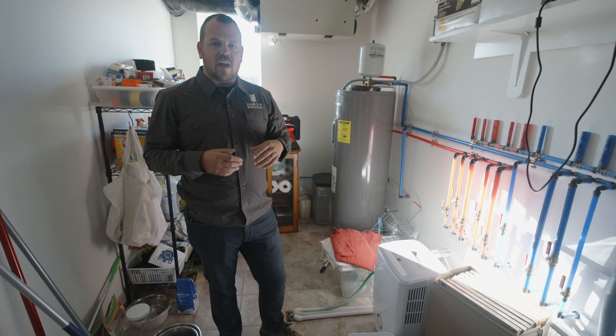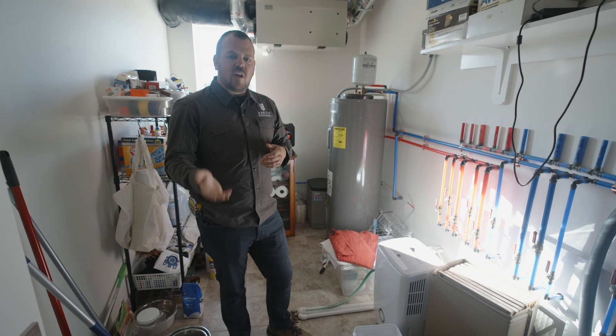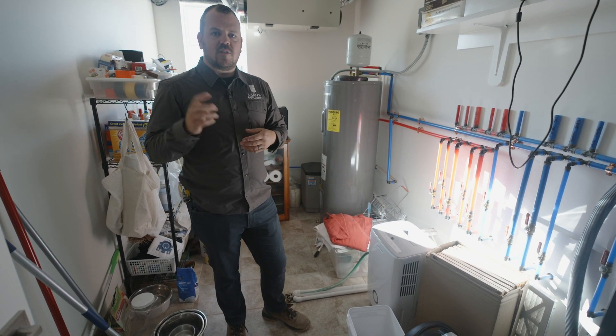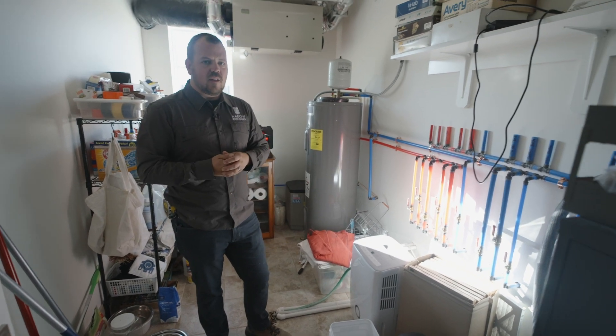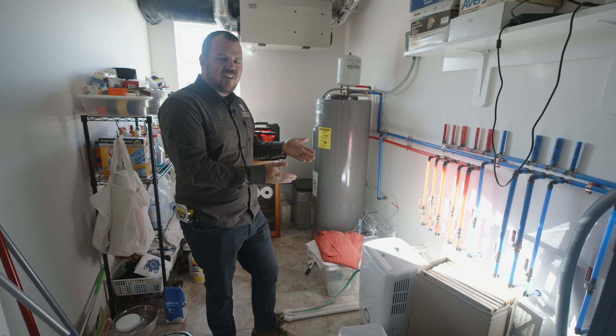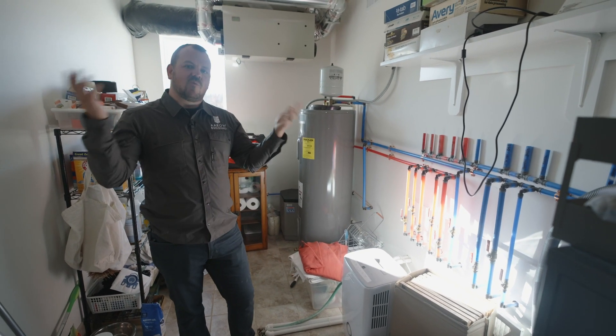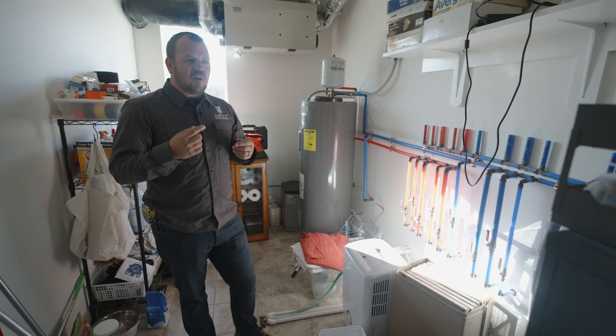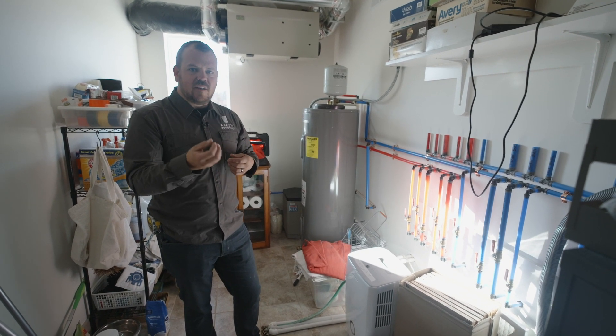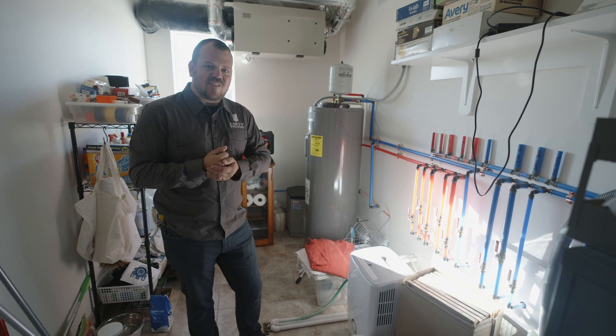About 10 to 15 minutes later in the conversation, the homeowner said, 'Oh, by the way, the dryer vent wasn't connected and we got it connected — you guys should think about using a different system for connecting your dryer vents because we didn't realize it wasn't connected.' And I was like, oh my goodness — this little 70-pint dehumidifier was literally taking care of the moisture load for their entire house from their dryer that's one room away, for months. And it was able to keep up because there was no other moisture input to the rest of the house. So while we planned everything correctly, we made one minor mistake in getting the dryer connected — and this little unit was still able to keep up. Now it doesn't run all the time; it just runs when it needs to.